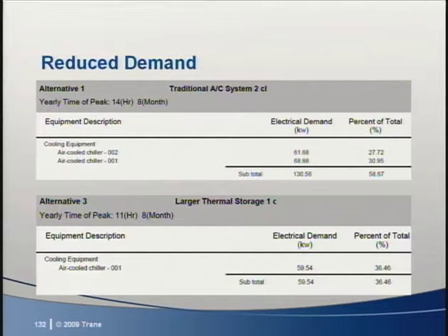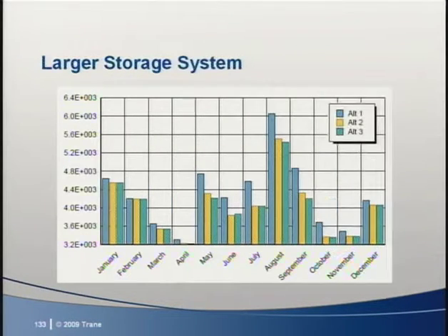So a reduction of 60 kW. At $13 each, that's $780 per month. While a 30% return on investment is tough to beat, sometimes we find that the lowest first cost system does not offer the most attractive return on investment. A slightly larger system might have been more beneficial in the long term.